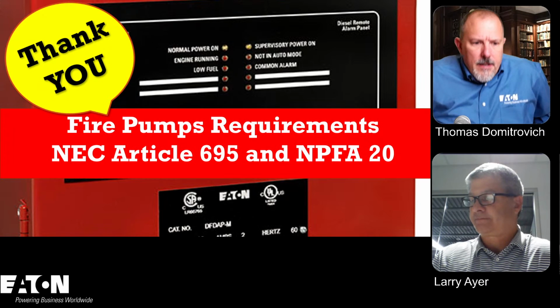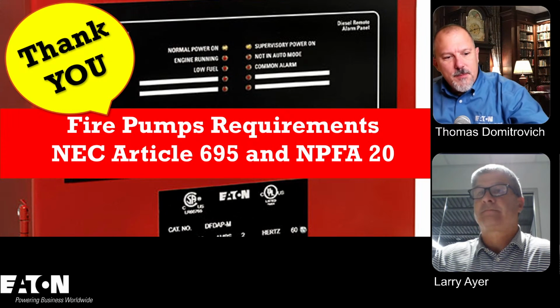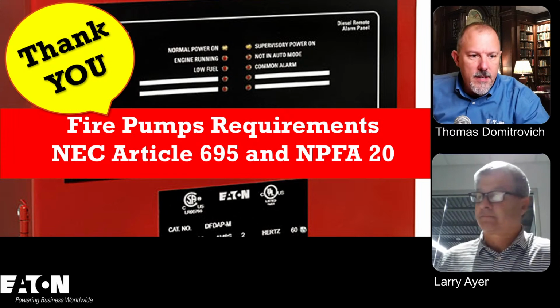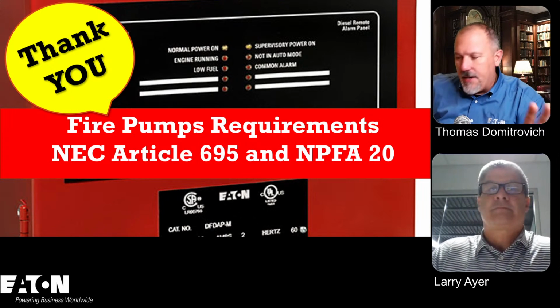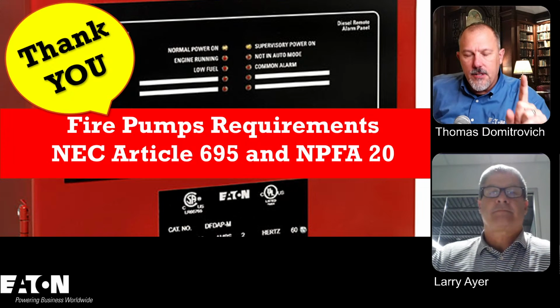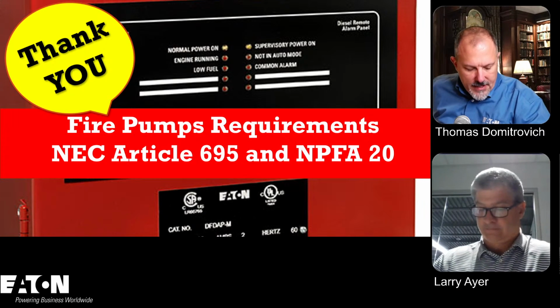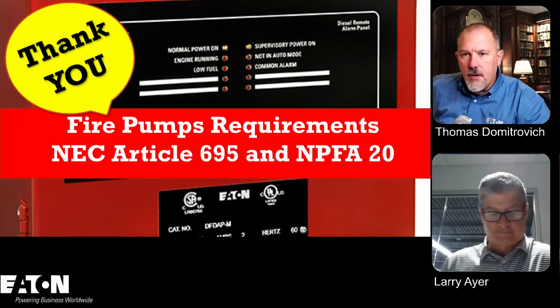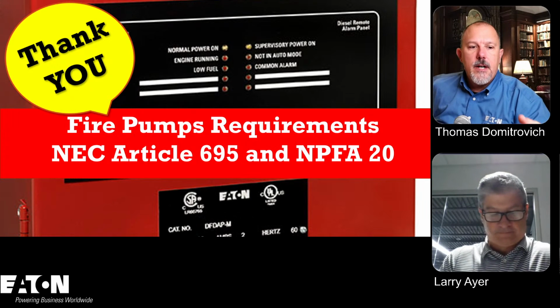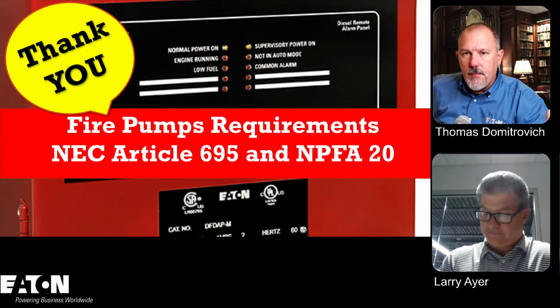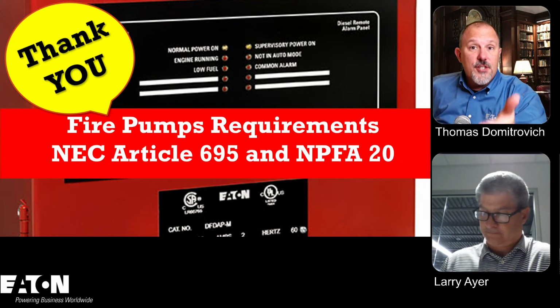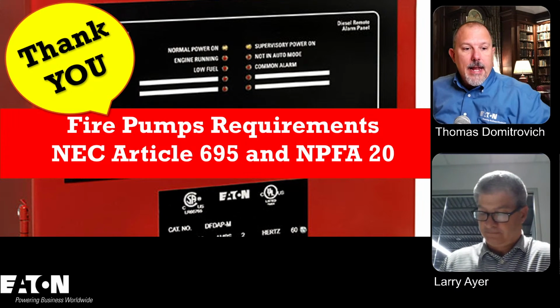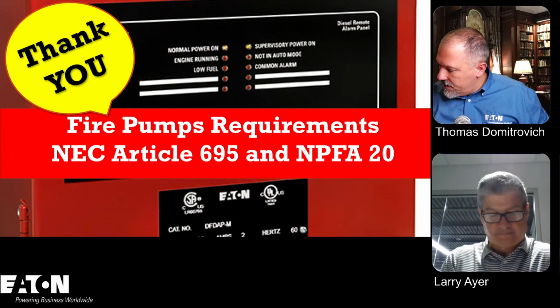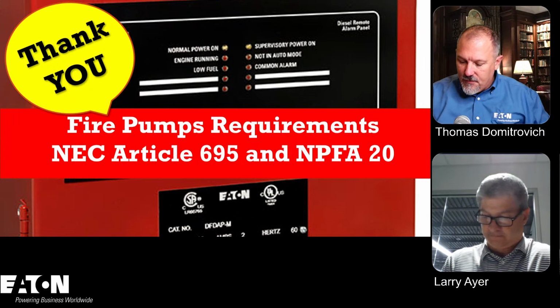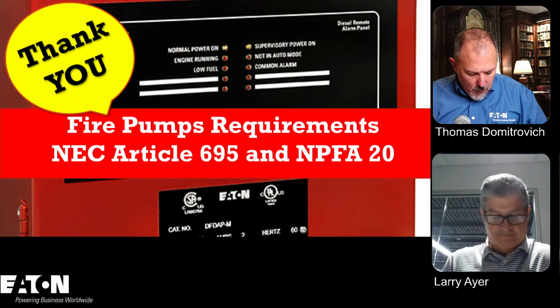Awesome. All right, so I was watching. There's some good dialogue. Jeff Fecteau came in, and when we were talking about the transfer switch and the listing requirement, Mather pointed out there's no listing requirement. Jeff said, "Hey, don't forget that 230.66 is going to require it to be a listed ATS, but that's listed as service equipment." And then he also pointed out 700 and 700.5, which I was looking at before.